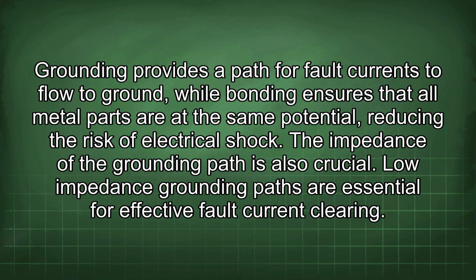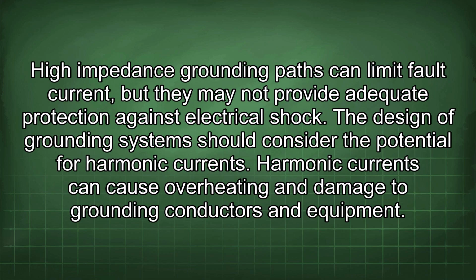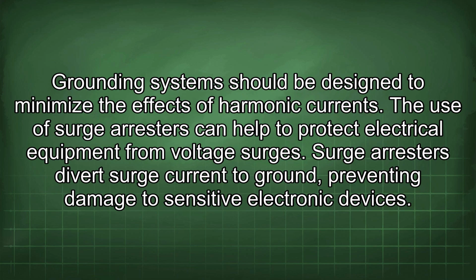The impedance of the grounding path is also crucial. Low impedance grounding paths are essential for effective fault current clearing. High impedance grounding paths can limit fault current, but they may not provide adequate protection against electrical shock. The design of grounding systems should consider the potential for harmonic currents. Harmonic currents can cause overheating and damage to grounding conductors and equipment. Grounding systems should be designed to minimize the effects of harmonic currents.